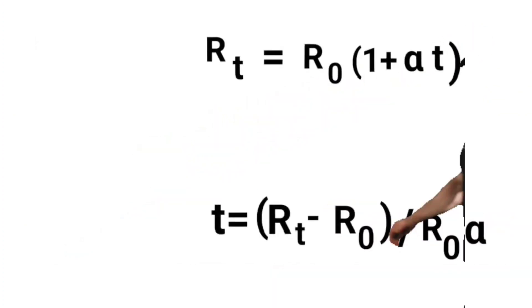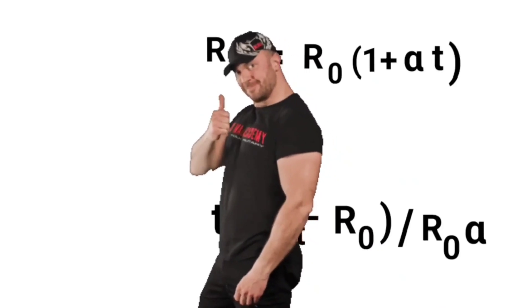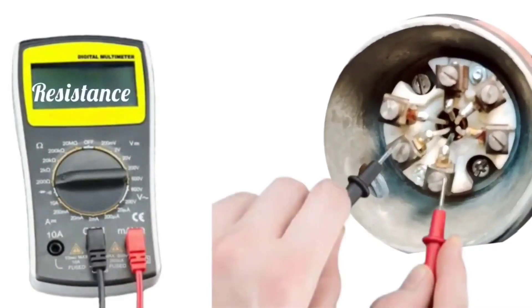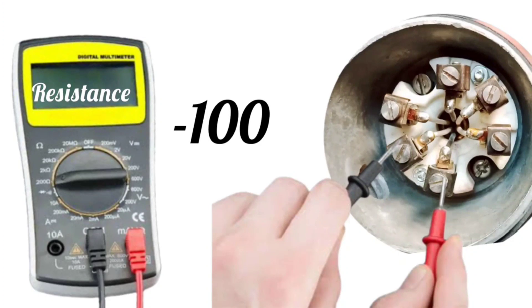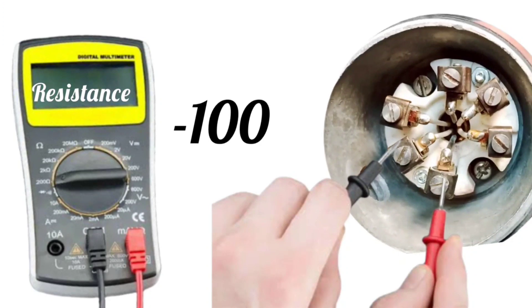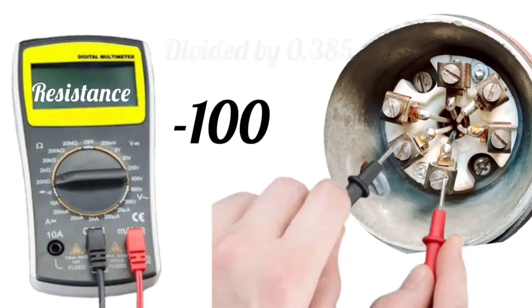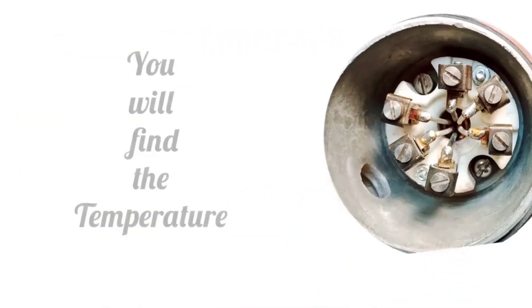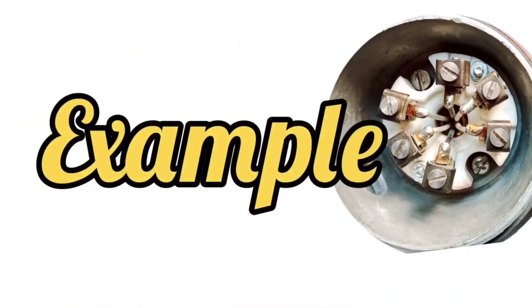Let us now understand the formula in easy language. There is no need to memorize long and elaborate formulas. As much resistance is being shown in the multimeter, minus 100 has to be done, and that has to be divided by 0.385 or multiply by 2.6. You will find the temperature. Let's understand this with an example.